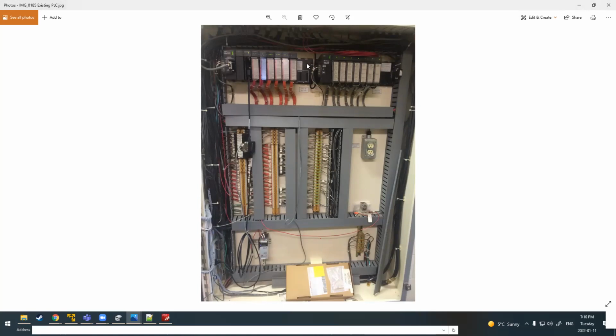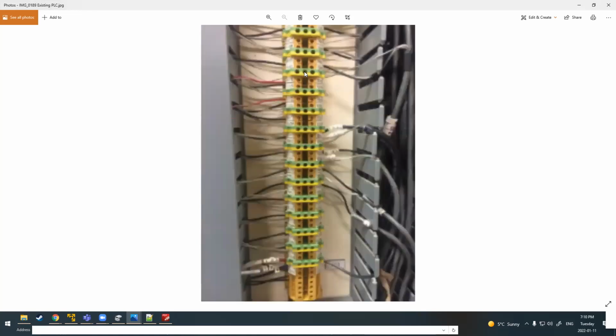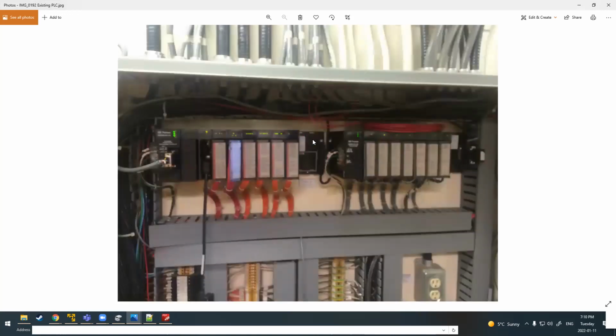So this black pad here at the back, let's see if we've got better photos. This is going to be the back plane for this one. This is the processor. So this is the PLC, that's the brain of it. And then these are going to be your digital input cards, your digital output cards. The rack, it looks like there's a remote rack here. So there's a crossover cable, which would then expand that rack onto the second one. And these are your analog input and output cards.